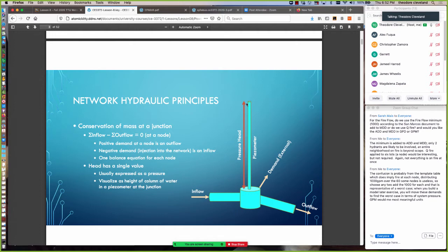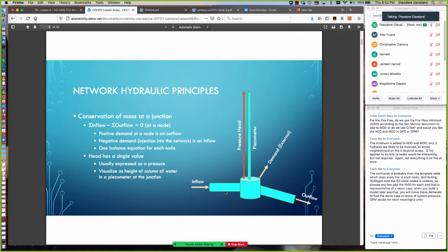The total head is really what we calculate, and then from the known elevations we recover the pressure head at each point, and then we can test that pressure head against our design guidelines, 35 psi for example, to find if our system is satisfying those requirements.